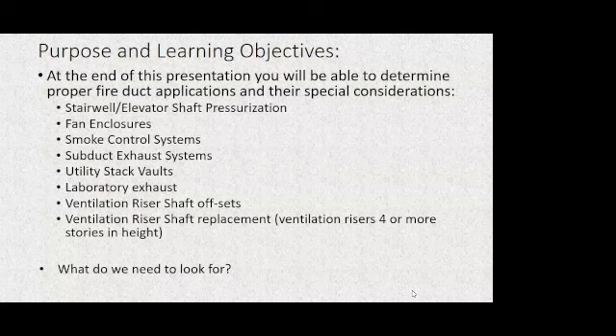And we can see that there are products out there that are fire rated for the enclosure of those fans when a dedicated fire-rated room for that fan cannot easily be programmed into the space plan. We have common smoke control systems using the four different methods: pressurization, exhaust, airflow. And we're going to talk a little bit, because it has context when we talk about the passive smoke control criteria in section 909 of the building code, and the parallel provisions within section 513 of the mechanical code.